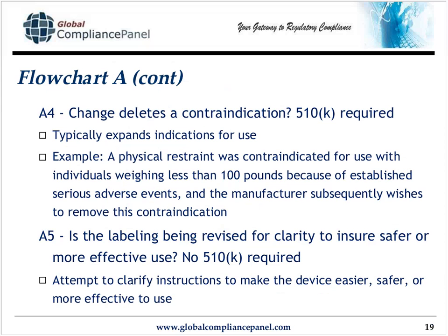So now what I'm saying is that you had to weigh less than 100 pounds to use it previously. And now I'm saying, no, you know what? Now anybody can use it. Well, I'm expanding the indications for use. I'm expanding the patient population. So now I've got to submit a new 510K.